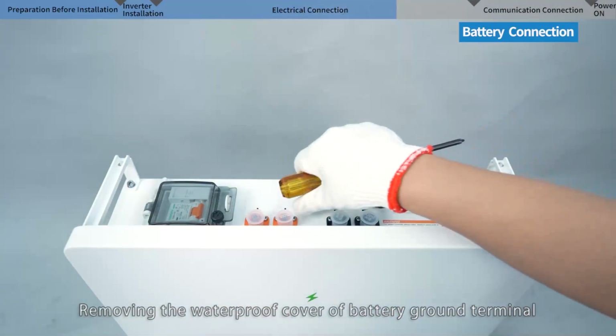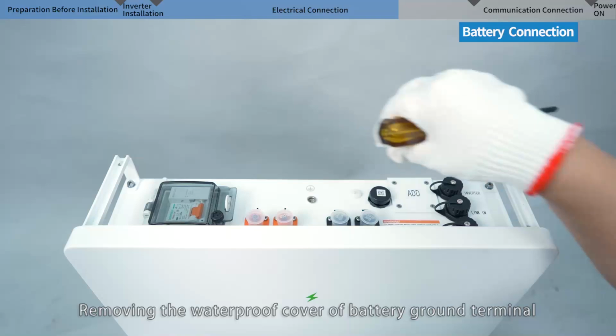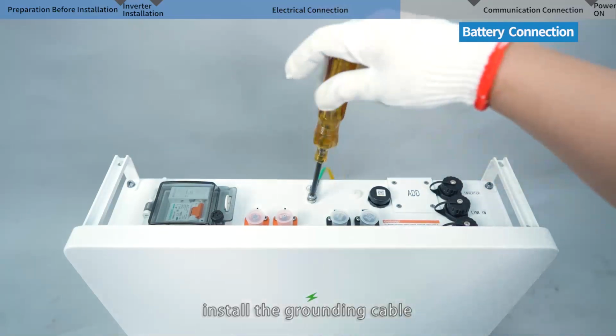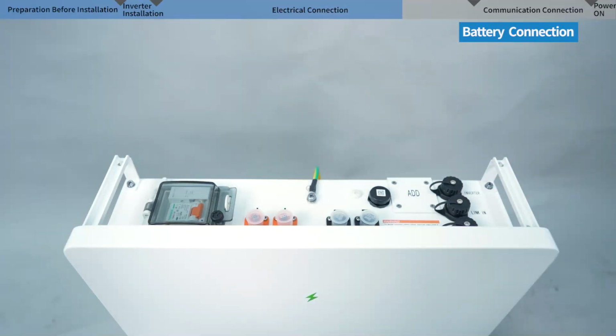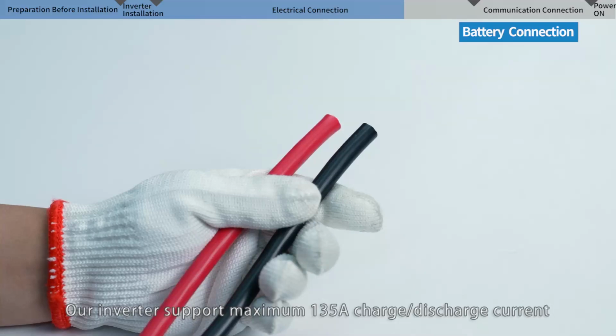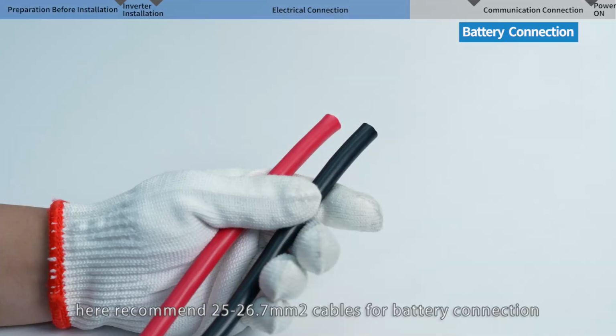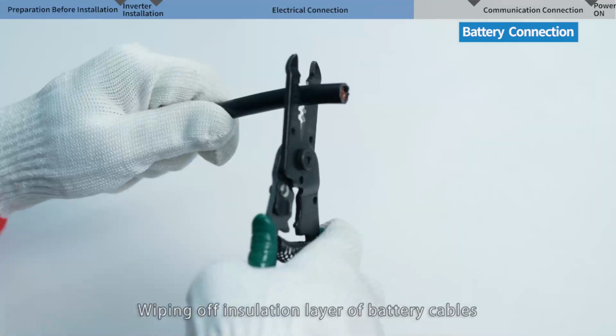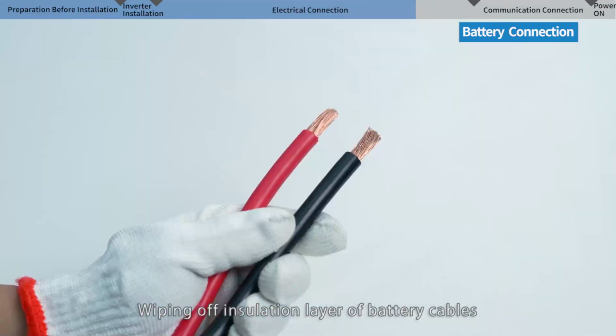Removing the waterproof cover of battery ground terminal. Install the grounding cable. Our inverter supports maximum 135 amp charge-discharge current. Here, we recommend 25 to 26.7 square millimeter cables for battery connection. Wiping off insulation layer of battery cables.